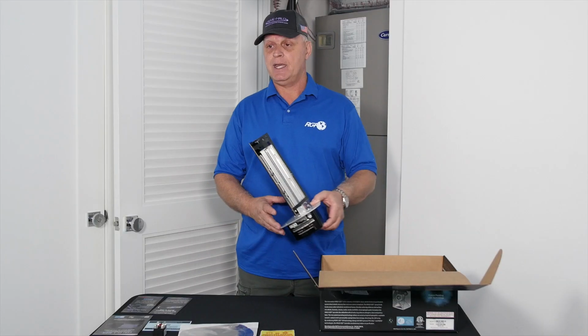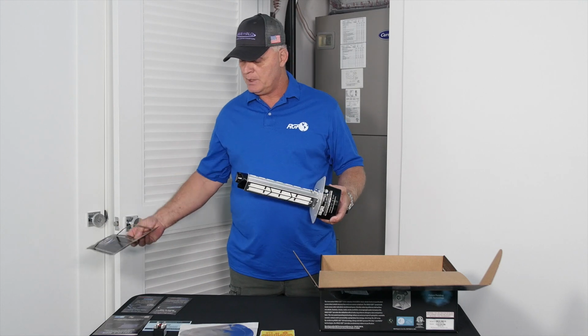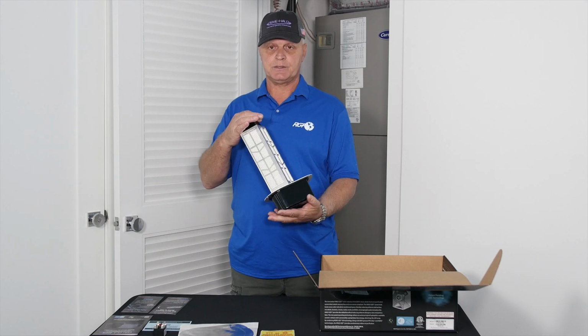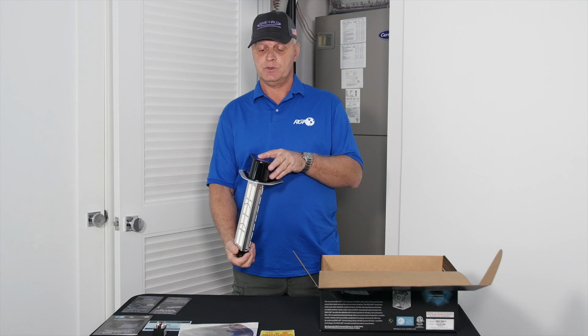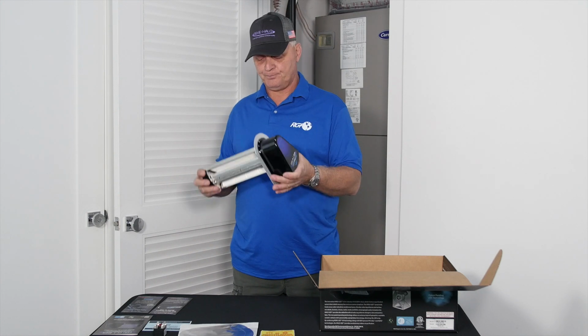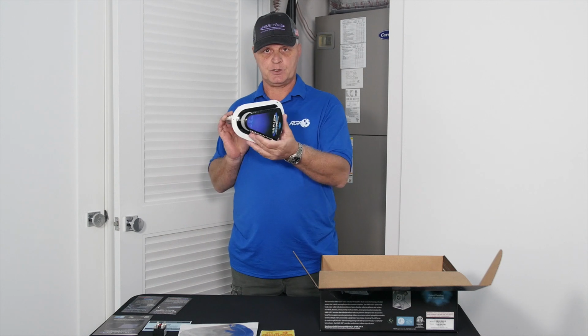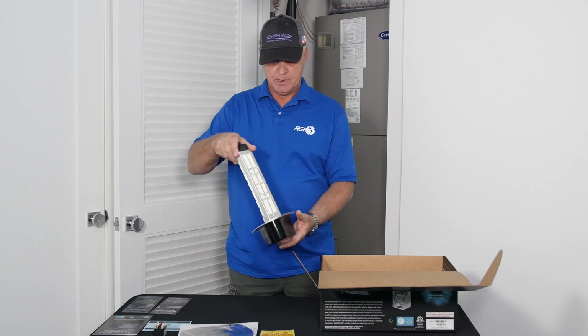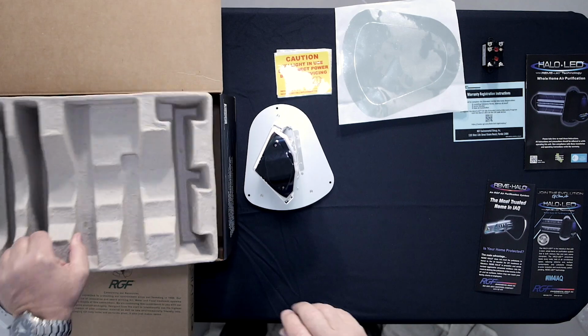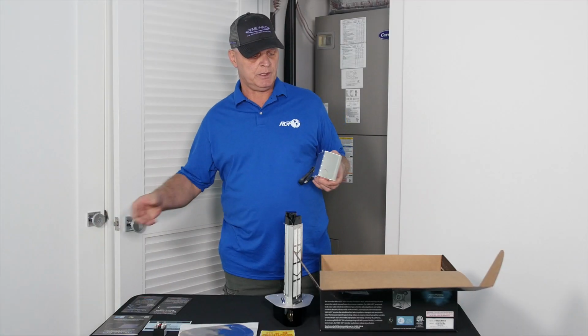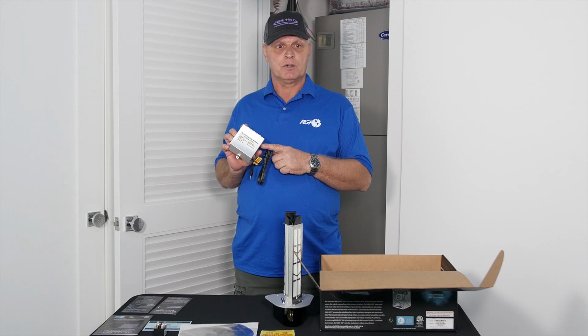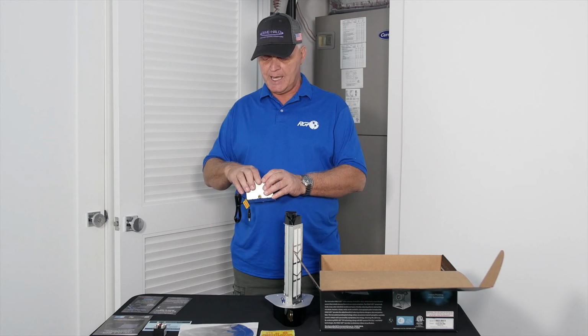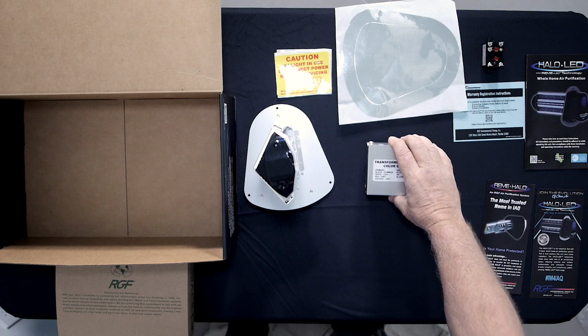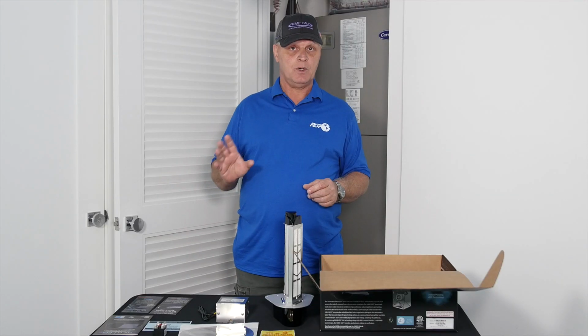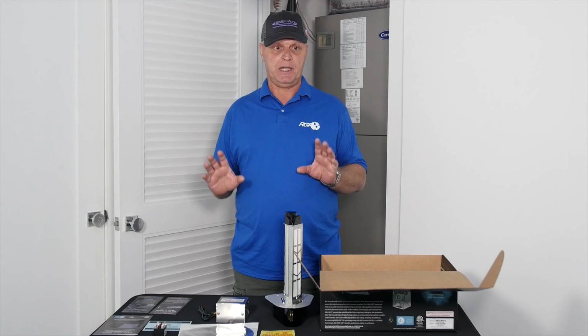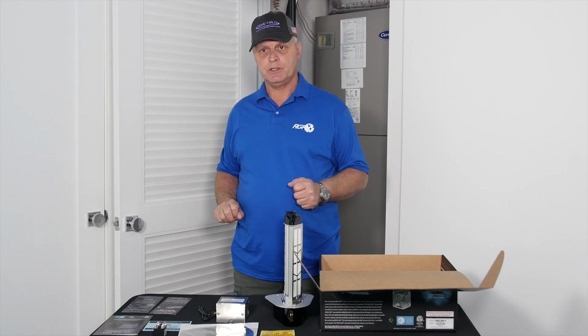This is the REME HALO LED unit itself. This is a directional airflow unit. As you see on the sticker on the top, it tells you your airflow has to be in this direction from the bottom up. And then in the bottom of the box, we have our power supply for the unit, which is a 24-volt transformer, a 40 VA. This unit can be wired for 120 volt, 208 volt, or 240 volt, depending on your air handler install you are using.